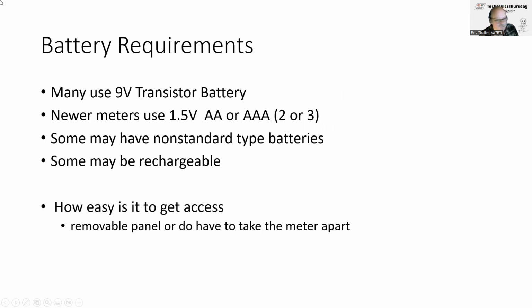Battery requirements - many meters use 9 volts or a transistor battery. Newer meters use 1.5 volts, usually a double A cell, 2 or 3 double A cells, or maybe even a triple A cell. Some may use non-standard type batteries, and some may be rechargeable. You want it to be fairly easy to get access to the batteries and the fuse - you don't want to take your whole meter apart to replace the fuse or the battery. Some meters are easier to take apart than others. Some you have to take the whole back cover off to replace the battery, while other meters you just unscrew it and out comes the battery compartment and you replace the battery.